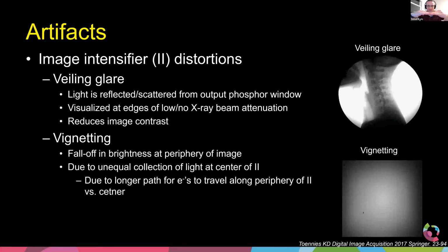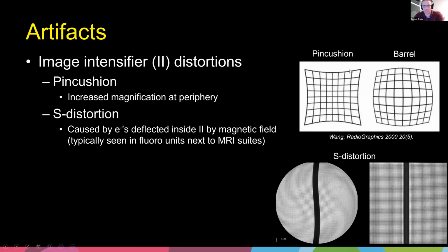If you have a flat surface, it would actually bow down. So engineering wise, you have to put it on a curve, and that structurally makes it strong enough to put a strong vacuum in there. But because you put a curve on your detector, you get the vignetting, where your signal is the strongest in the center, weakest at the edge, but then you also get this blur, this distortion, a pincushion distortion or a barrel distortion.